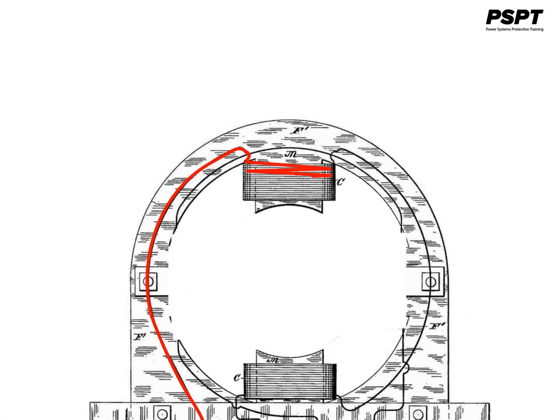Single-phase induction motors suffer from a severe handicap. Since there is only one phase on the stator winding, the magnetic field in a single-phase induction motor does not rotate. Instead, it pulses, getting first larger, then smaller, but always remaining in the same direction. Because there is no rotating stator magnetic field, the single-phase induction motor has no starting torque. A single-phase induction motor is not self-starting, but requires some additional means of getting it started.